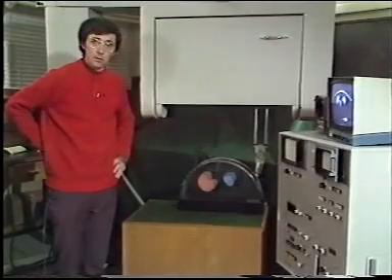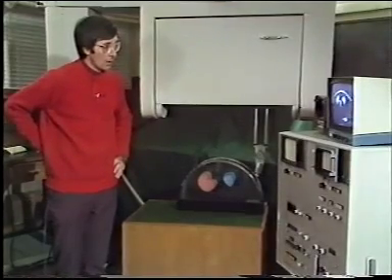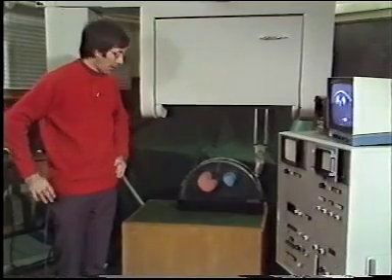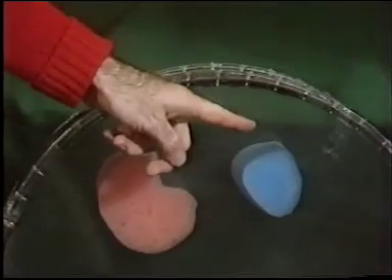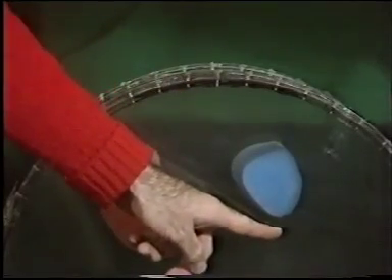As in the fetus inside the human uterus, a large part of this picture contains no information because a large part of the volume of the model, as the volume of the uterus, is water or amniotic fluid in the case of the uterus. And a way of improving the resolution of the picture, the information content, is essentially to amplify the part we're interested in by cutting out signals that are reflected either from above the object of interest or from well below the object of interest.